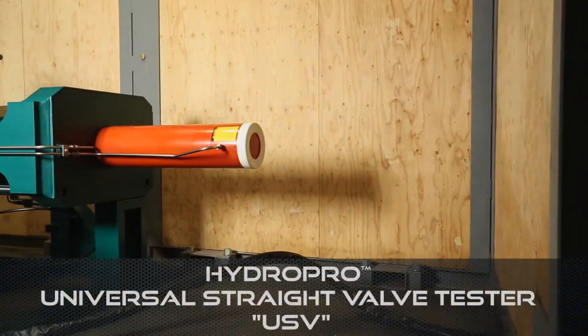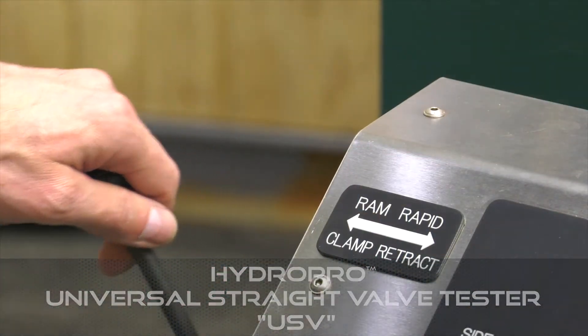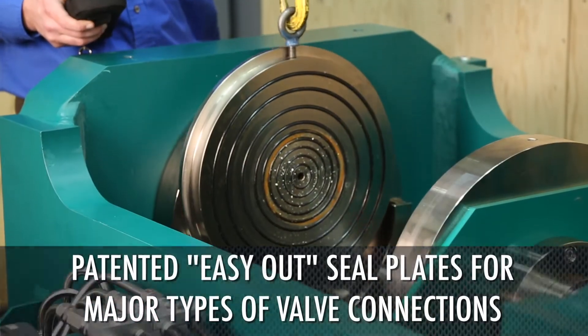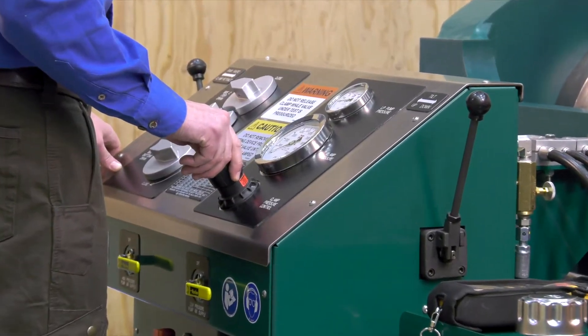Connect the HydroPro console to the universal straight valve tester for efficient testing of straight path valves. High and low RAM speeds with patented easy out seal plates ensure fast clamping and leak free connections. The USV allows installation, clamping, and hydraulic loading of the valve in the horizontal axis.